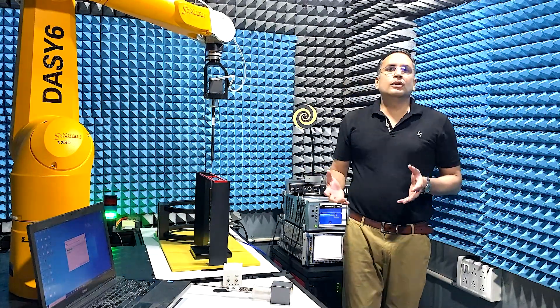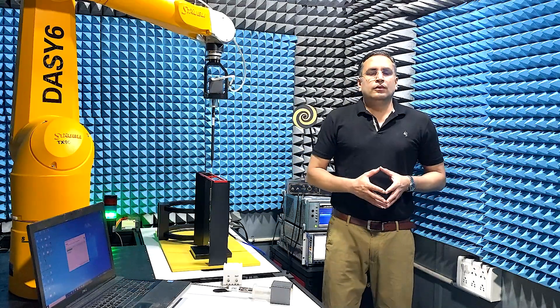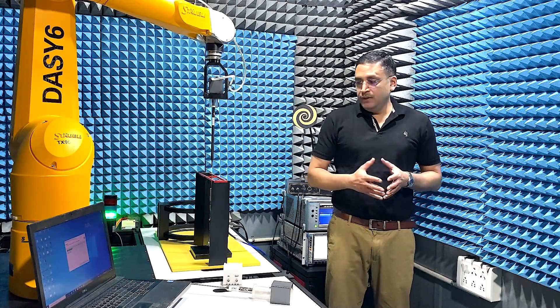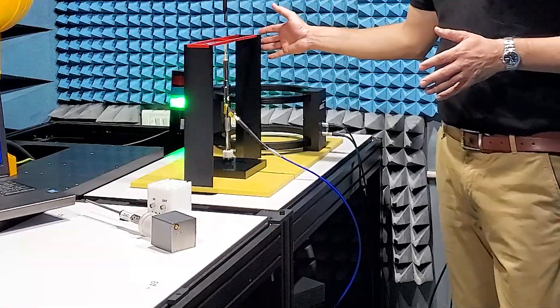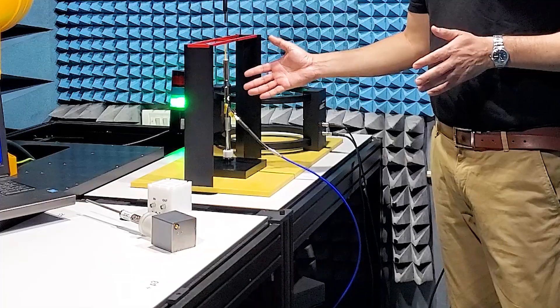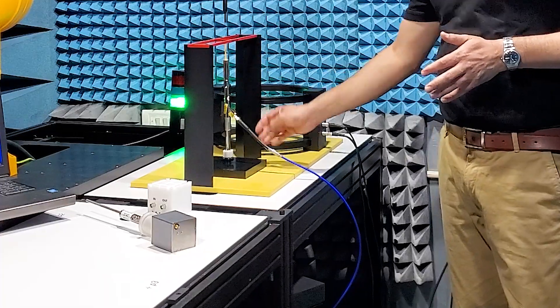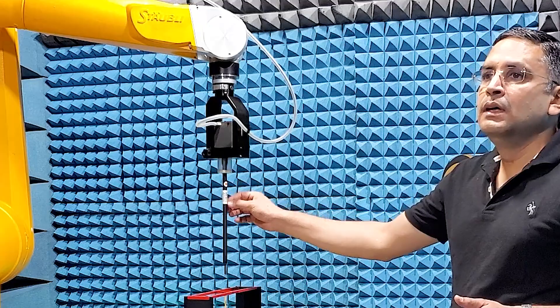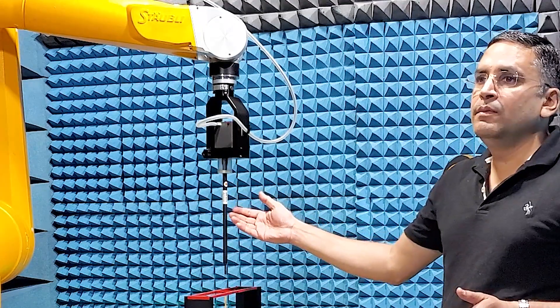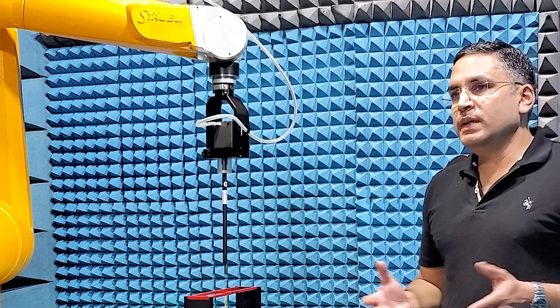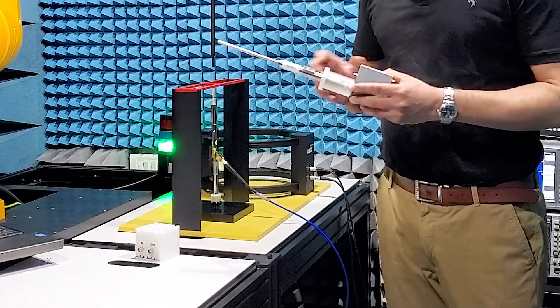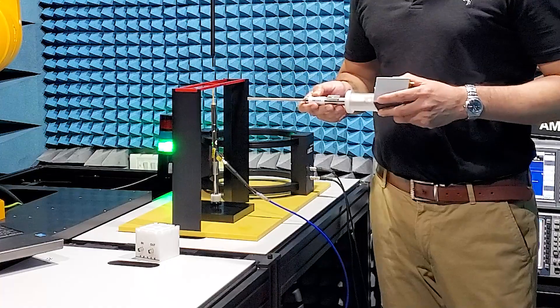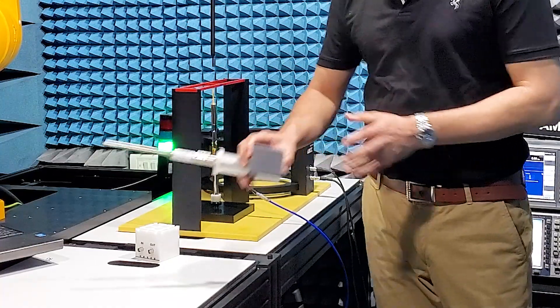Module HAC 2019 is fully compatible with the existing HACK hardware. We have here the arc phantom for placement of dipoles or devices under test with the associated holders. E-field probes such as the EF3 for radio frequency or RF emission measurements. Audio magnetic field probes such as the AM1-DB3 for T-coil measurements.